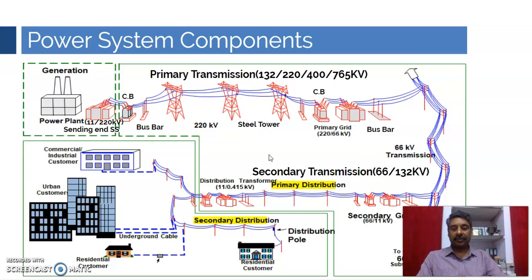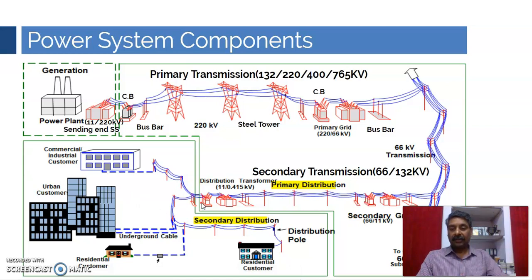This is called primary distribution. Secondary distribution serves urban as well as residential customers, done at maximum 11 kV or 33 kV for commercial customers. For residential customers, supply is at 11 kV, which is then stepped down to 415 volts. For example, if you are residing in an apartment complex, in the cellar you will find a transformer. Up to the primary side of the transformer, electrical energy comes in at 11 kV, and below that the voltage drops to 415 volts on the secondary side.